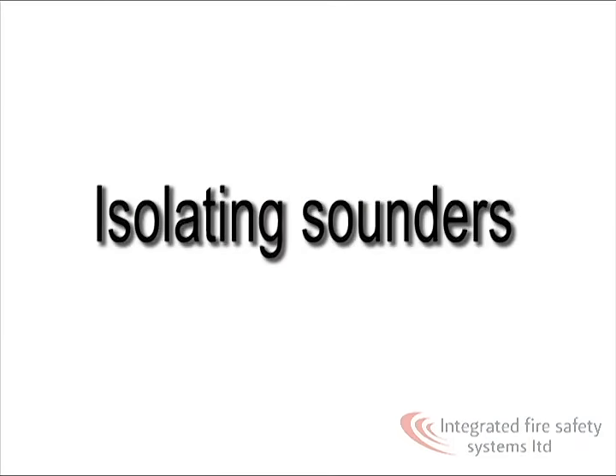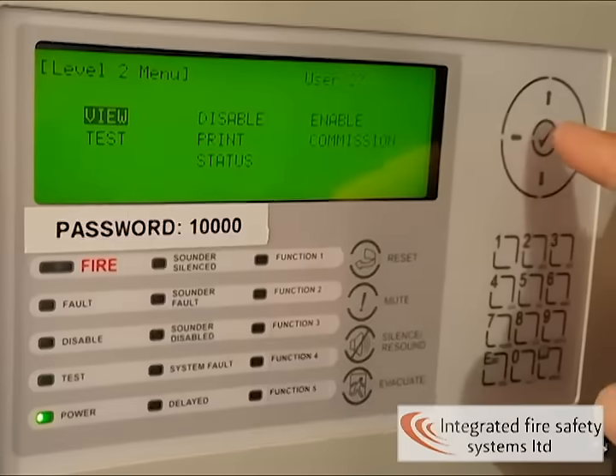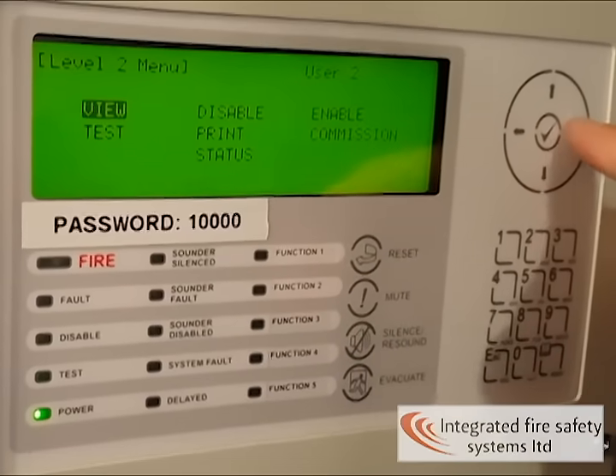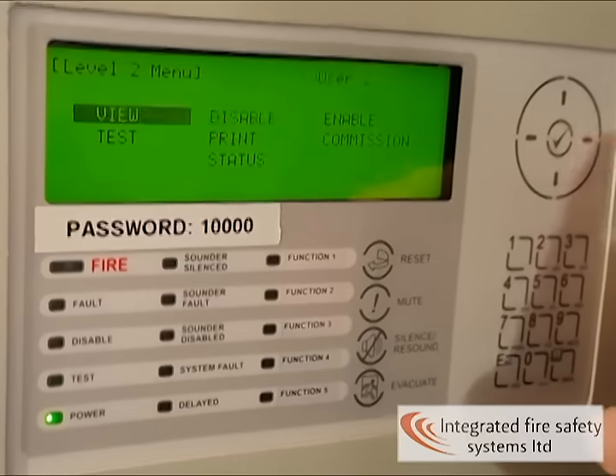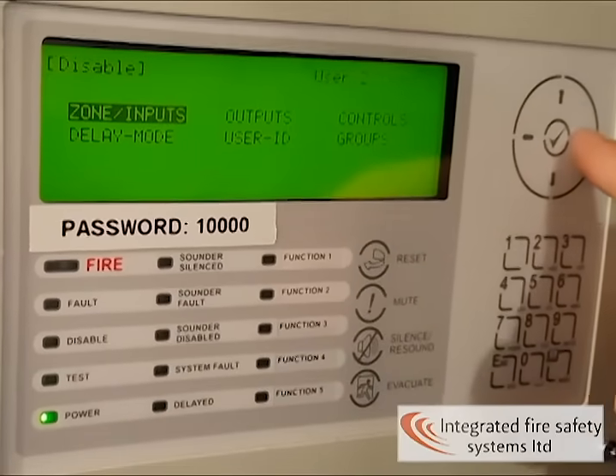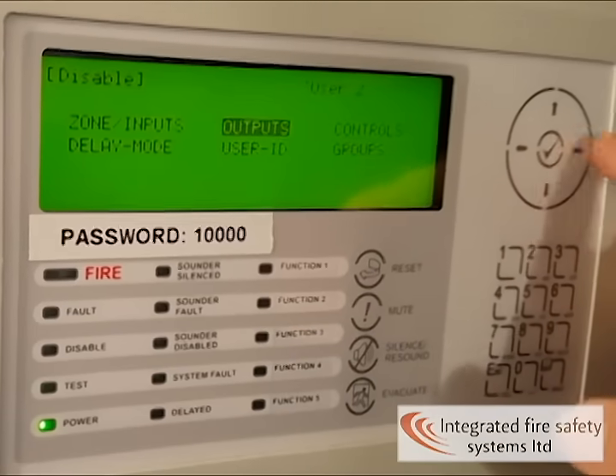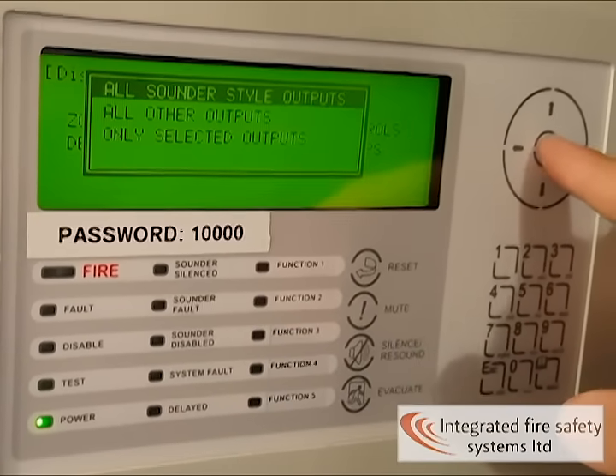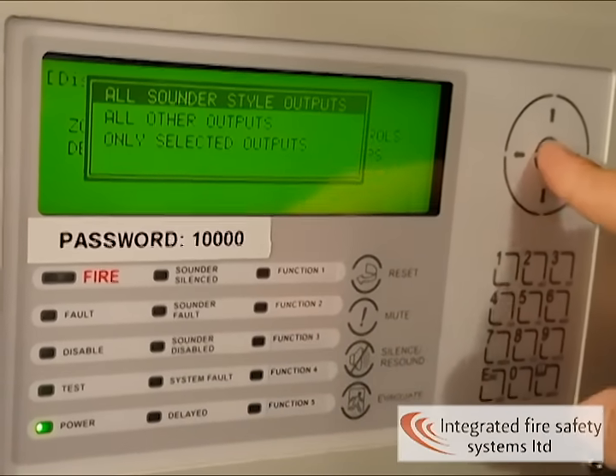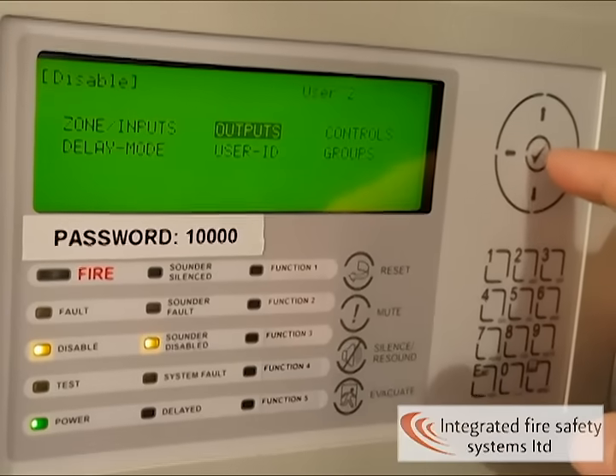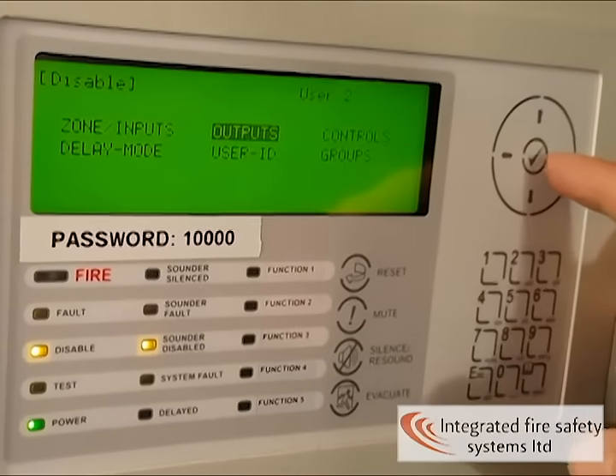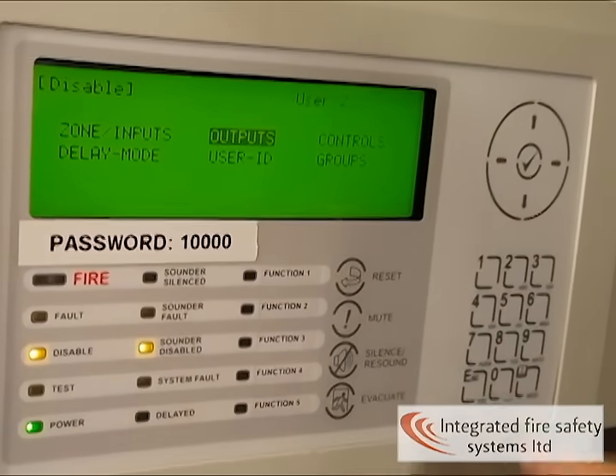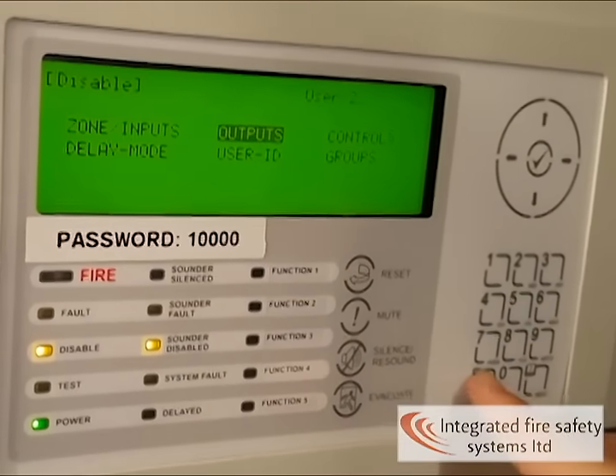To isolate sounders, follow the same process to access user level 2. Go to disable, tick, zone outputs, tick, and then the panel will give you options to select all sounders. By pressing tick again, you'll see the orange LEDs light up on the panel, and now you can simply escape out of the user menu.